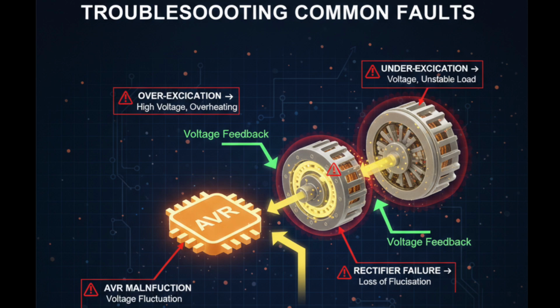2. Under-excitation, low voltage due to rotor field failure or exciter issues, causing poor load sharing. 3. Rectifier failure. If a diode fails, DC supply to the rotor is interrupted, and the generator cannot produce rated voltage. 4. AVR malfunction causes fluctuating voltage, unstable frequency, and may trigger alarms. Notice how the graphics allow you to visualize fault locations. For example, red flashing on the rectifier diodes shows where current flow stops.